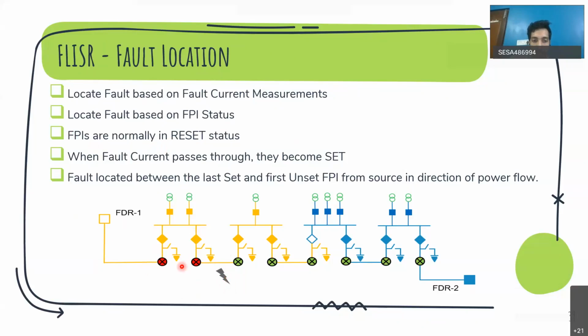So this will get set and this will get set. This will not get set. It will continue to be in reset position because fault current is not passing through it. So the fault will be located between the last set and the first unset FPI from the source in the direction of power flow. This is first, this is second, so this is the last set, and then the first unset FPI. So this is in unset condition, and that way it will identify that this is the faulty section.